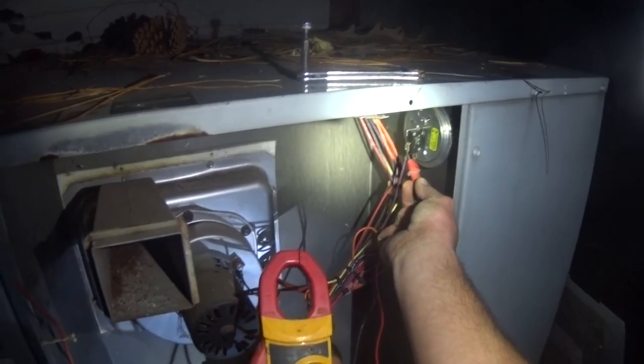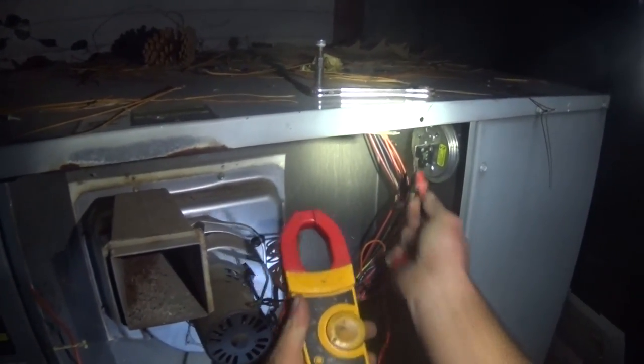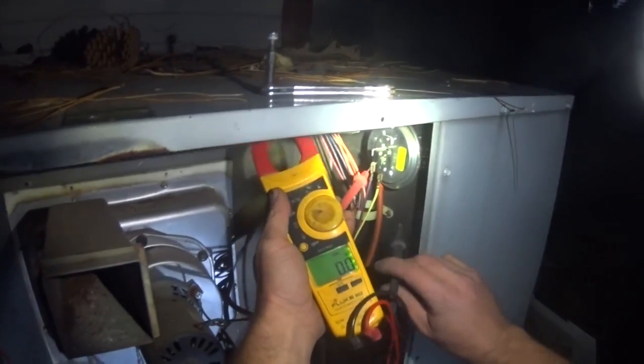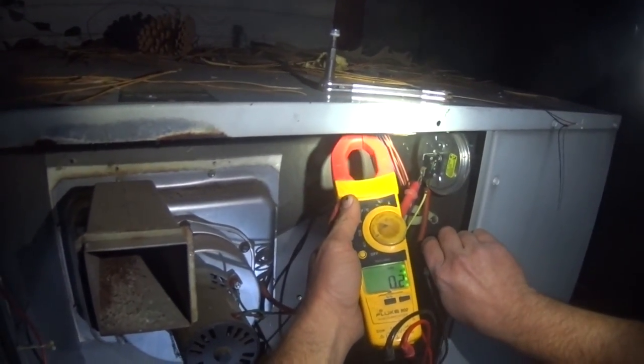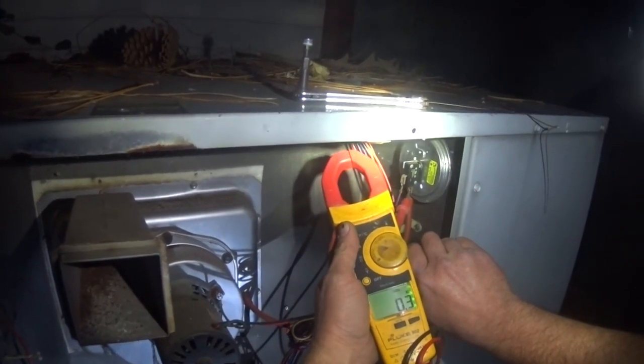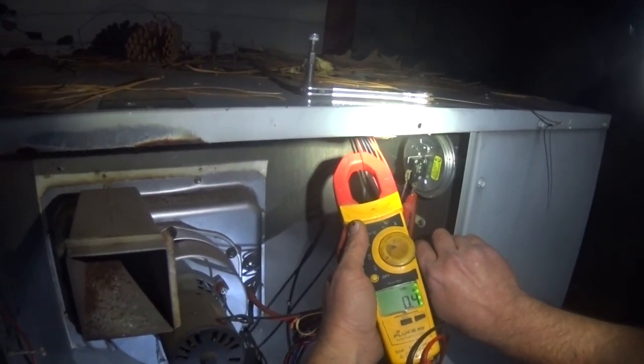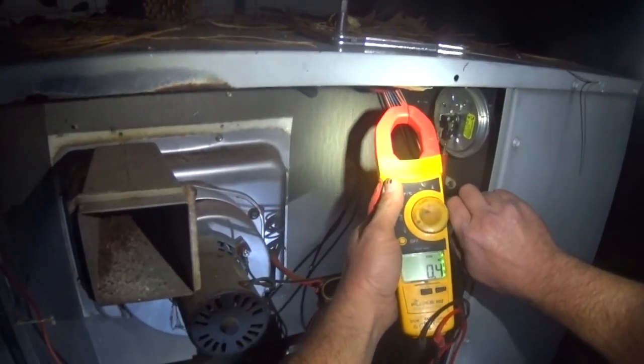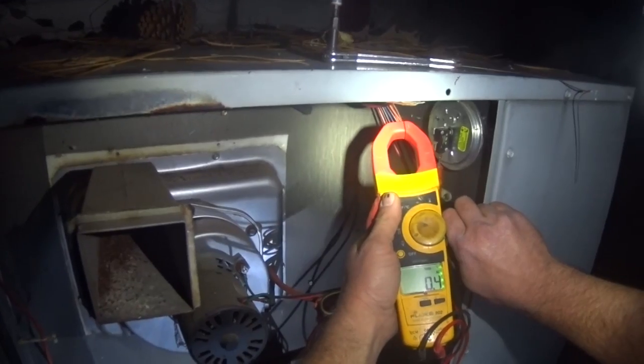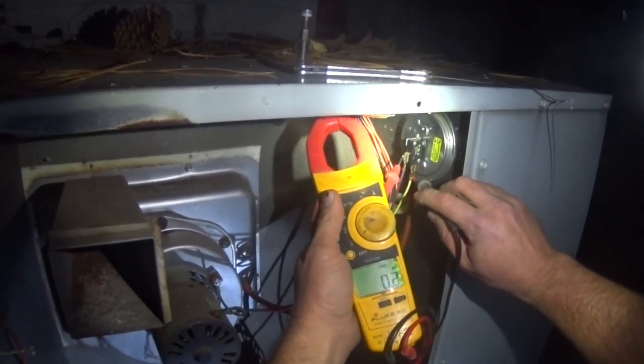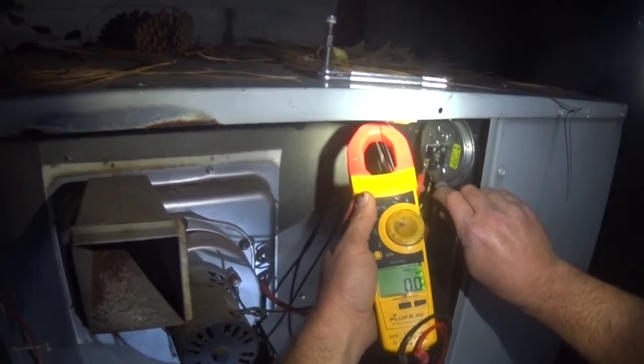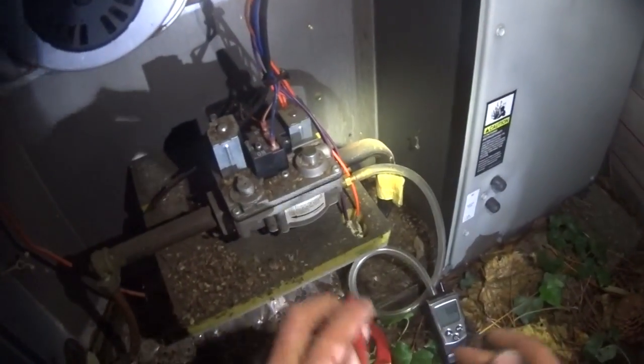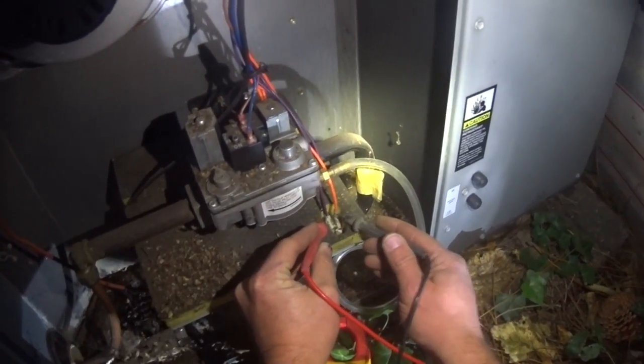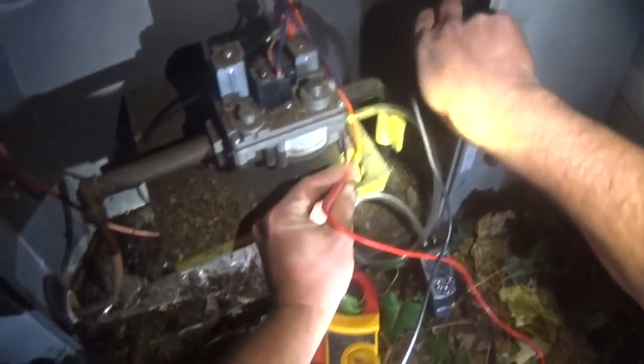Got no voltage across the pins, which means that it should be closed. And if we check each leg to ground, we got nothing there, nothing there. Interesting. Normally 0 across the pins would mean that the pressure switch was closed, but we actually have no voltage at all. So we are losing our voltage somewhere previous to the pressure switch.